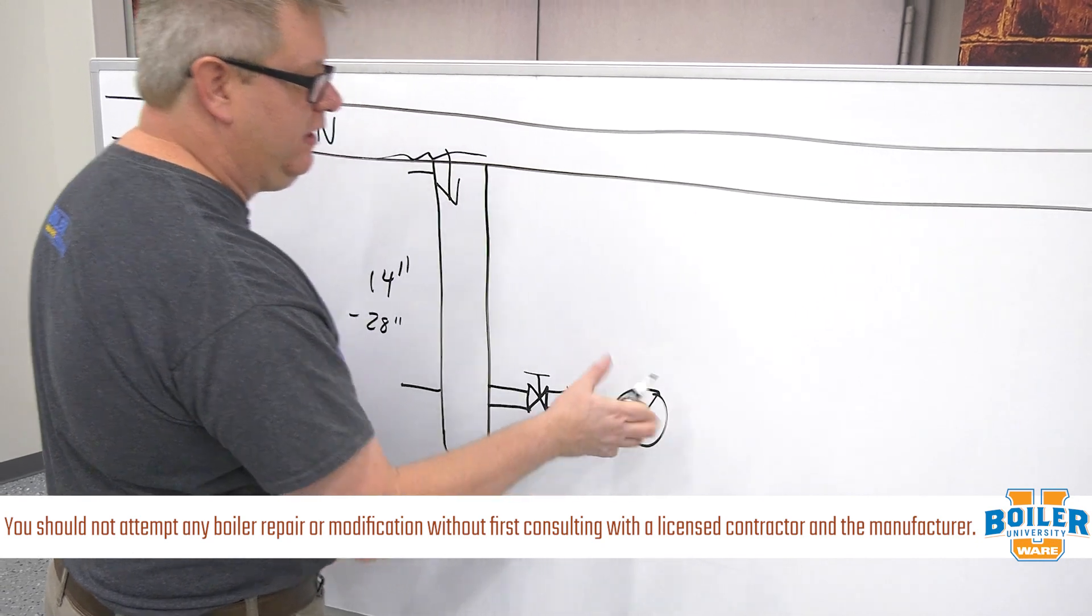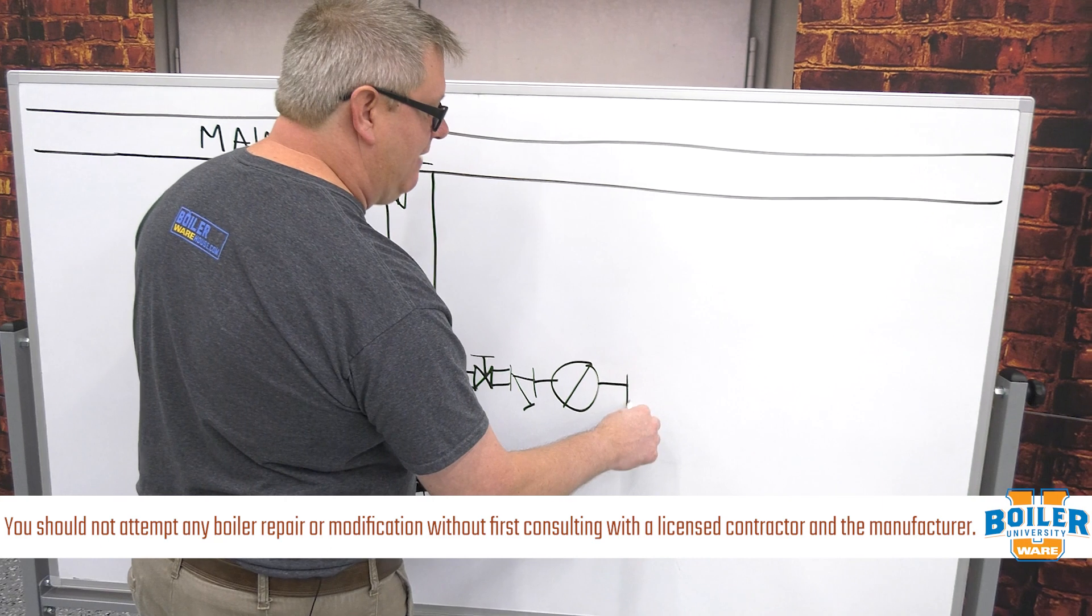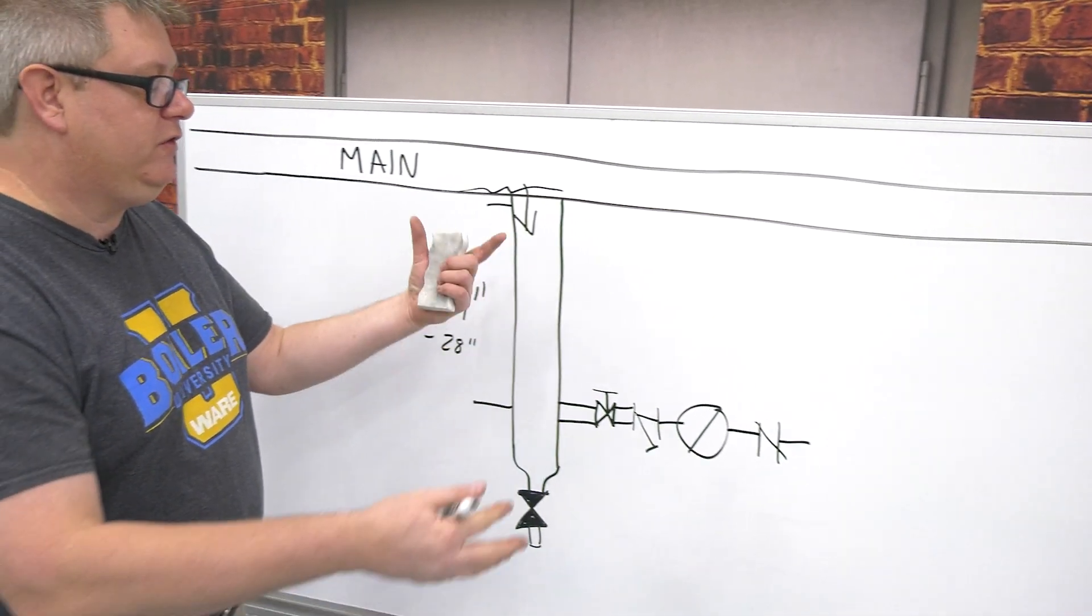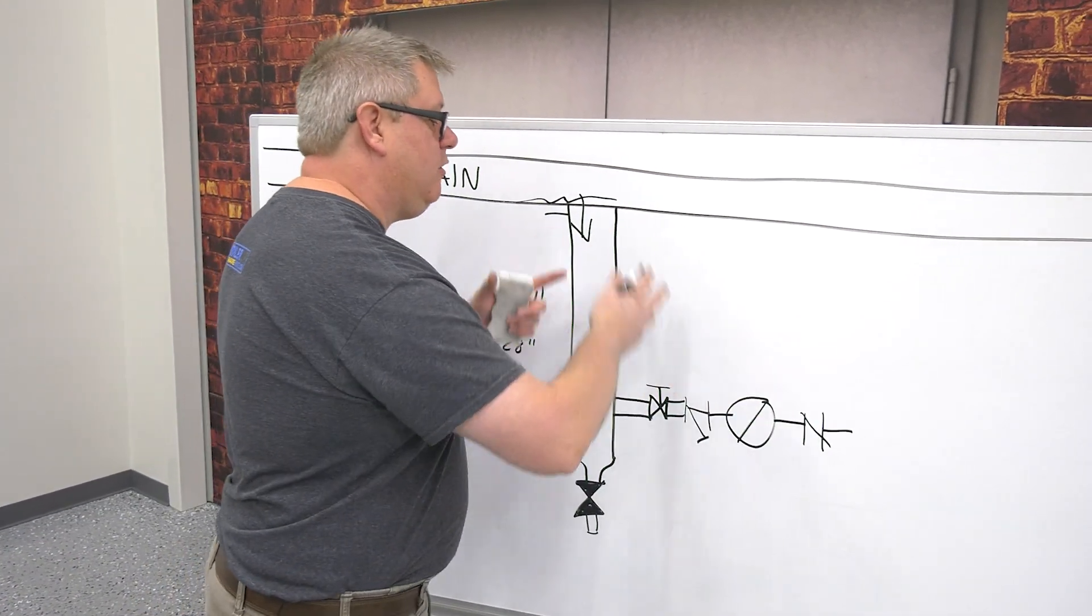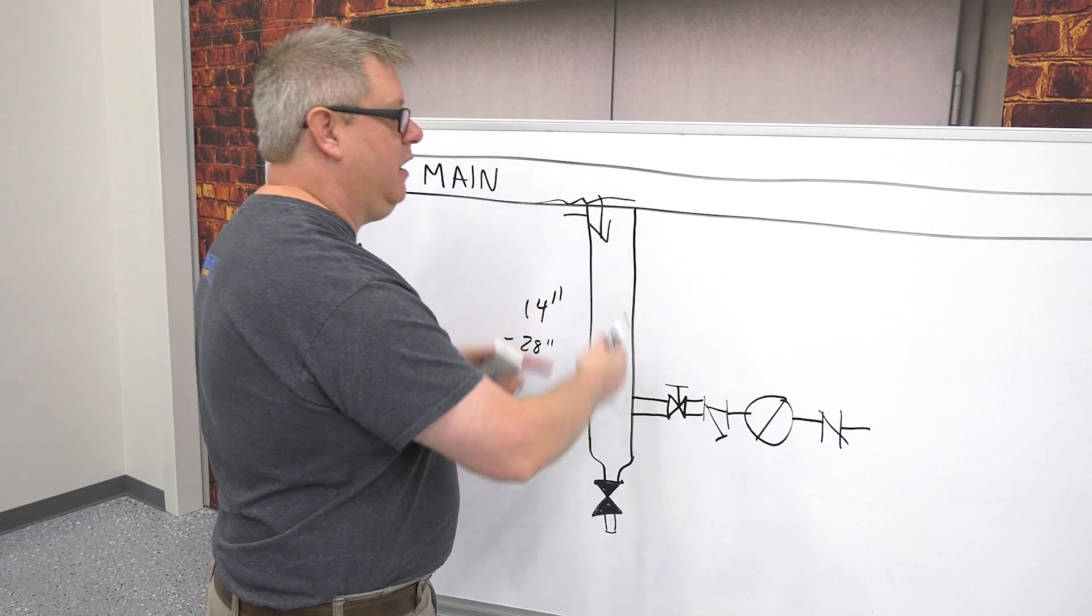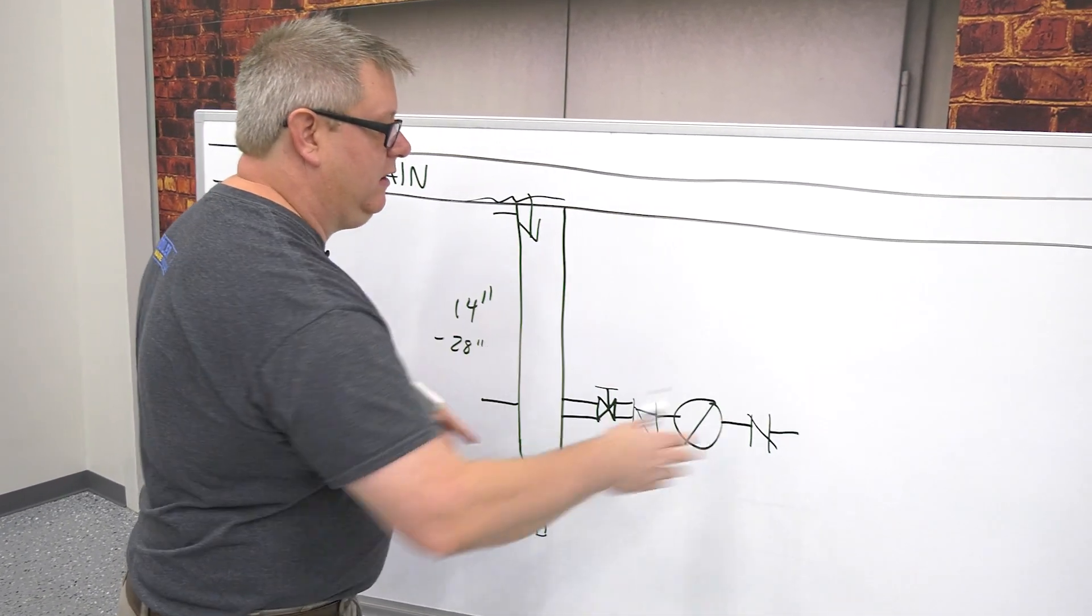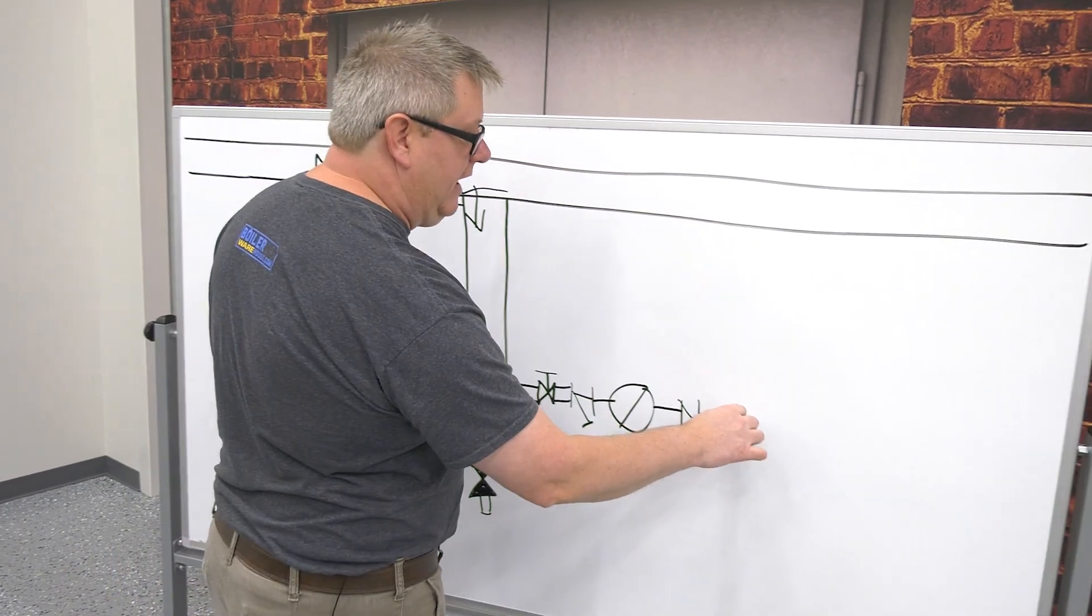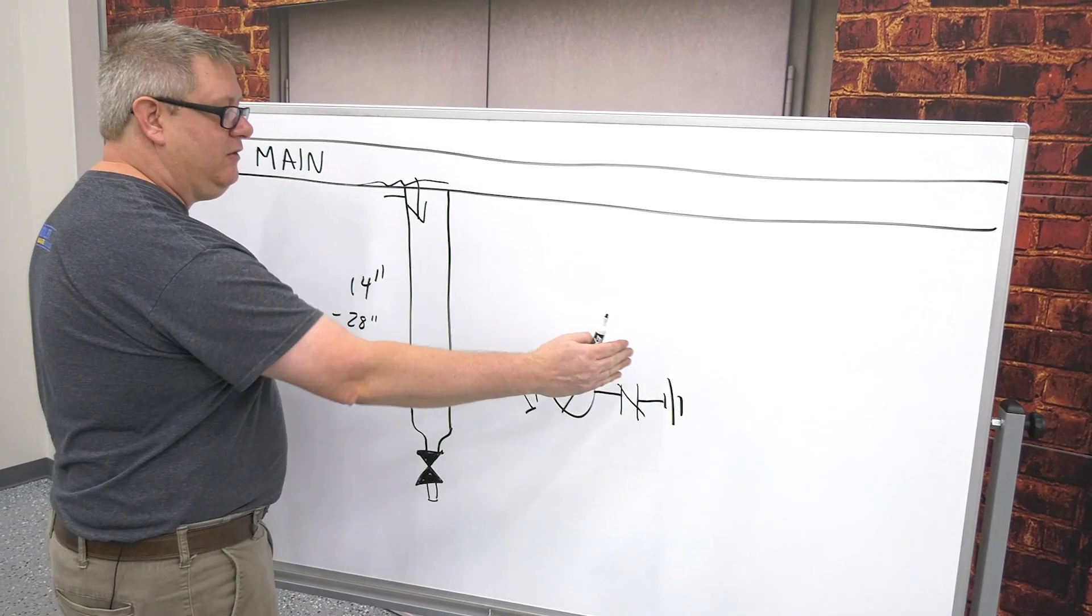On the outlet of the trap, we're going to have a check valve. And the benefit of a check valve on the outlet of a trap is when the system's shutting down, there's no way for the vacuum in the steam system to suck condensate back into the header. So it's just there to make sure everything only goes in the correct direction. We're generally going to have a union so that we can disassemble this as needed.